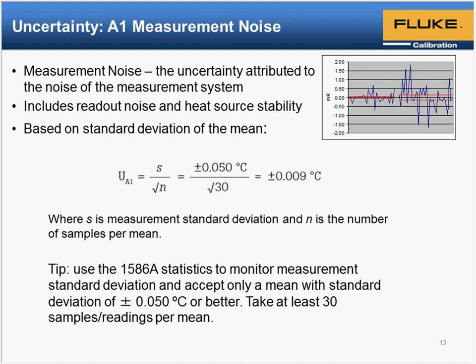But ultimately, the principle is related to taking multiple readings. It's good practice in every calibration scenario to take more than one reading so that a mean can be calculated rather than just a single reading. And we would like to measure at least 30 readings on the reference probe to calculate the mean temperature that the reference probe is indicating.